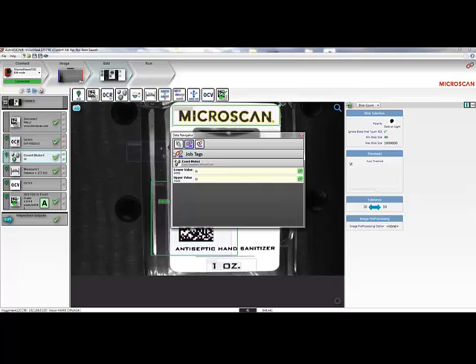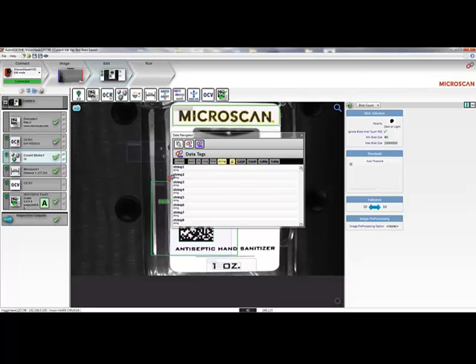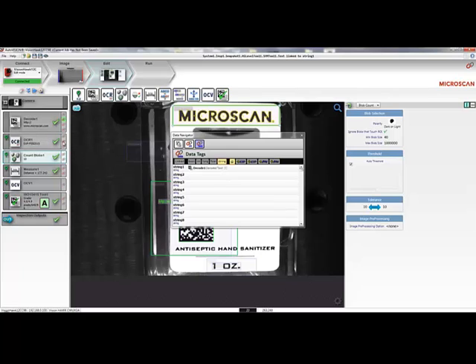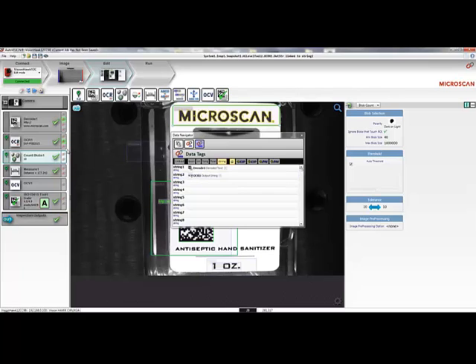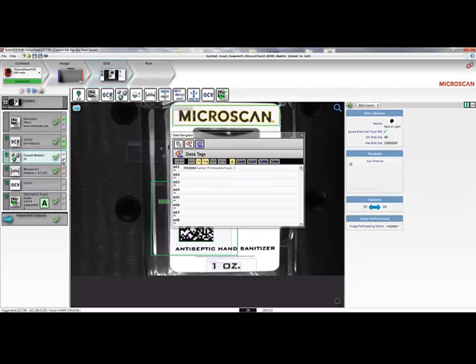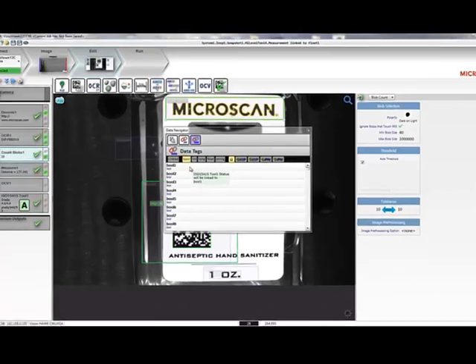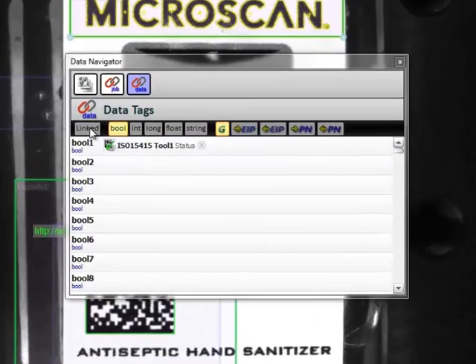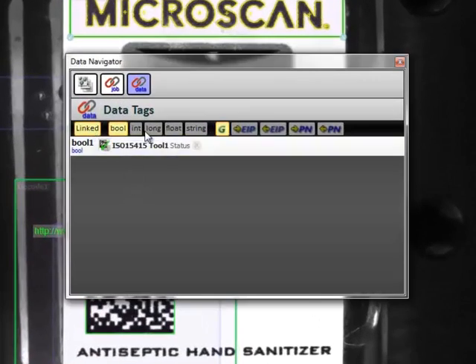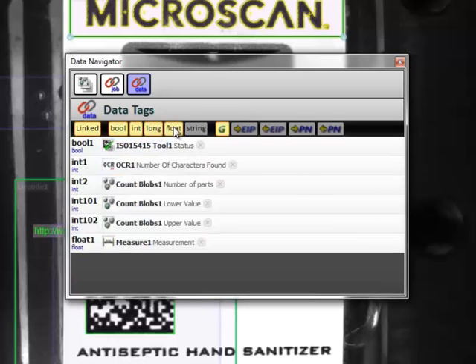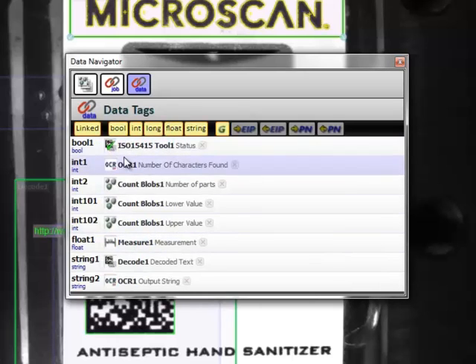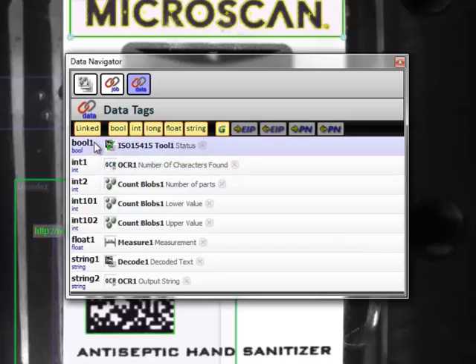I can do the same thing with output values. For example, I can take the decoded string from my decode tool and drag it to string number 1, linking it to the outside world. I can take the output string of the OCR tool, link it in the same way. I can take my OCR character count and link it to Integer number 1. I'll take the Count tool count and link it to Integer number 2. I'll take the output from the Measure tool and put it in float point number 1. And lastly, I'll take the status of my Verification tool and link it to a flag on Boolean 1. Now, if I look at all of the linked values in the Data Navigator by including all value types, you can see all of the output values that I've linked and the two input values that are linked.